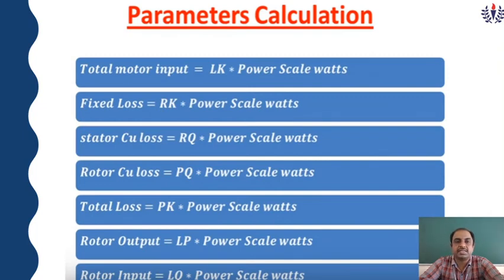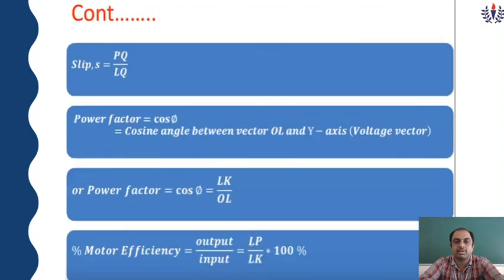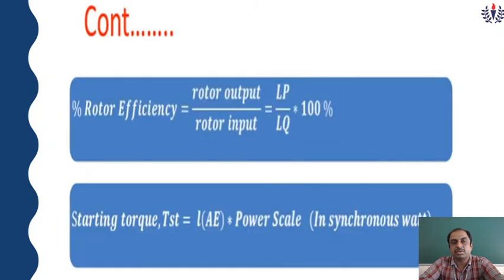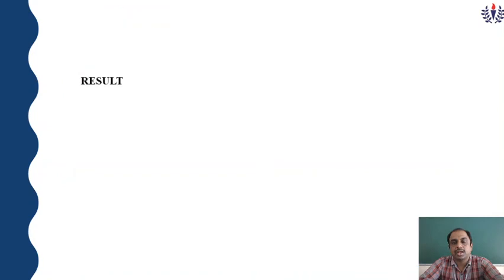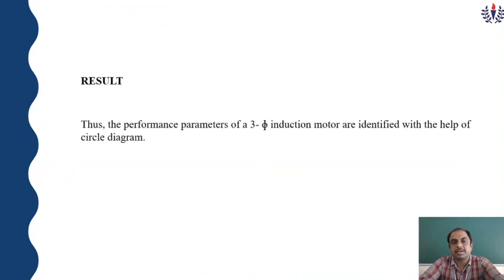The parameter calculations are: total motor input, fixed loss, stator copper loss, rotor copper loss, total loss, rotor output, slip, power factor, motor efficiency, rotor efficiency, and starting torque. The main result of this experiment is that the performance parameters of the three-phase induction motor are identified with the help of the circle diagram. Thank you.